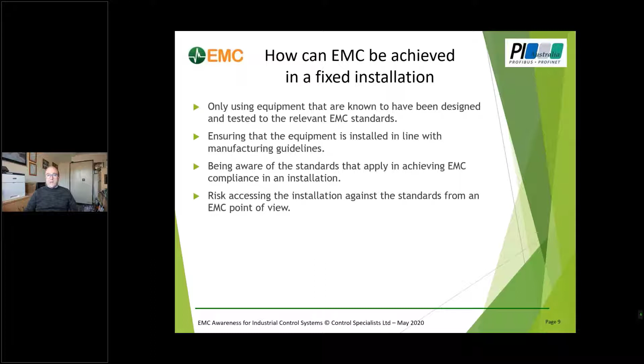Being aware of the standards that apply to EMC compliance in an installation is where we're going to start. Risk assessing the installation against the standards, because these standards cover a very wide range of situations, and your situation may not come under that guide—so what's the point of spending money fixing a problem you're not likely to get?